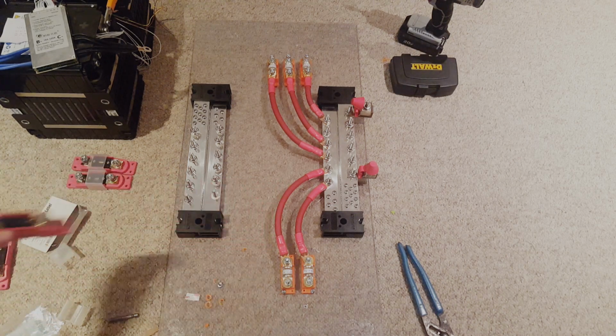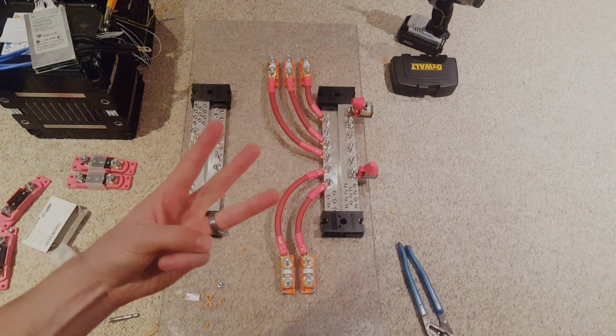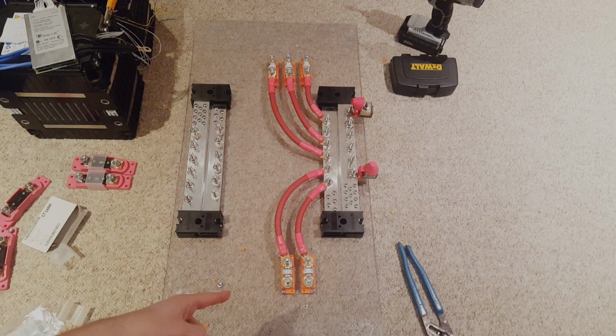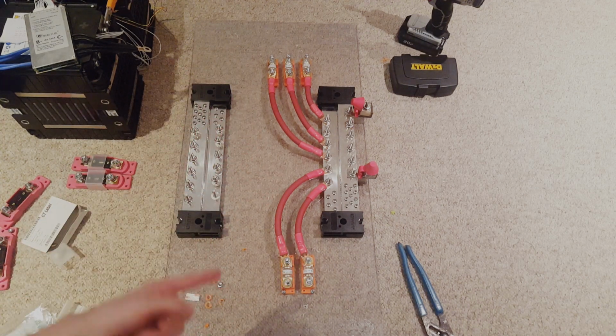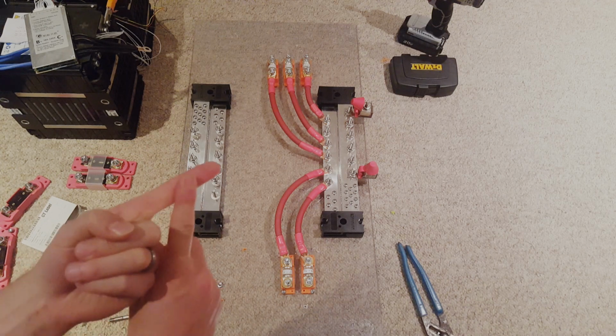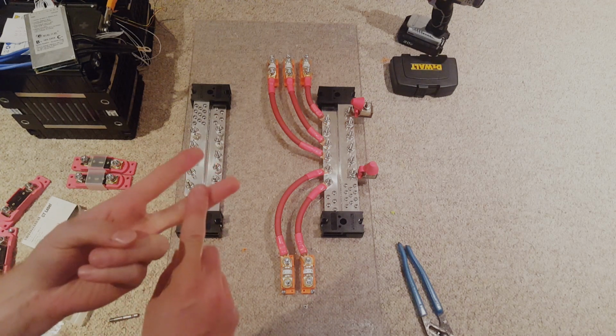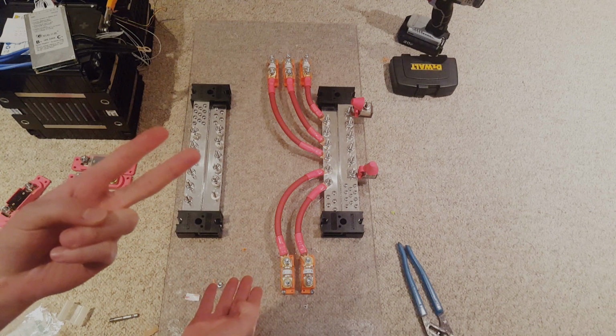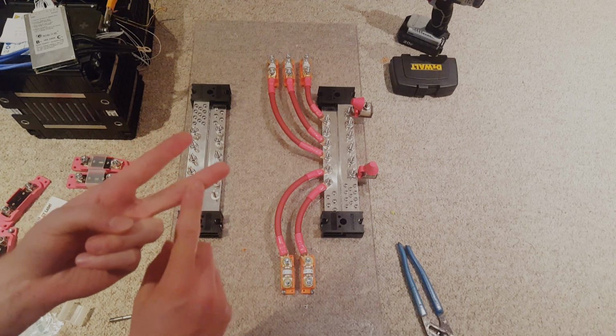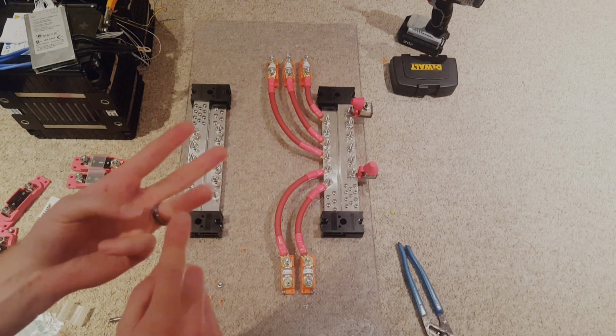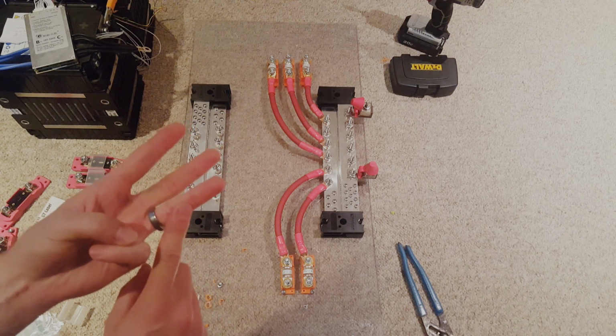So you really need to factor in 3 major things when you're determining what size and type of fuse to use. It's going to be the voltage that you're going to be operating at. It's going to be the interruption current, which these are 100 amp fuses. So the interruption current minimum, and then the maximum current that these fuses may see.